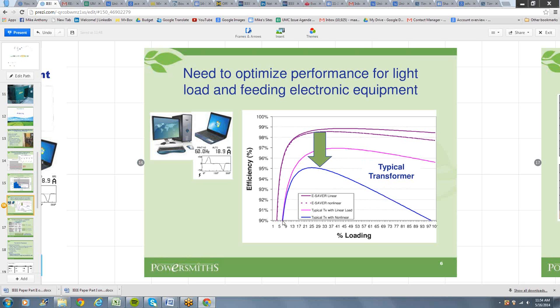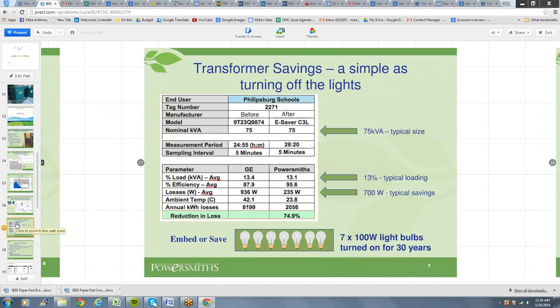So really, if you're going to provide a transformer that's suitable today for the application and you're going to deliver real-world savings, you've got to come up the efficiency curve very quickly at light load, and then you've also got to minimize that gap going from linear to nonlinear load, which you can see is achieved at the top transformer. And that's really what you're looking at in order to make things work today.